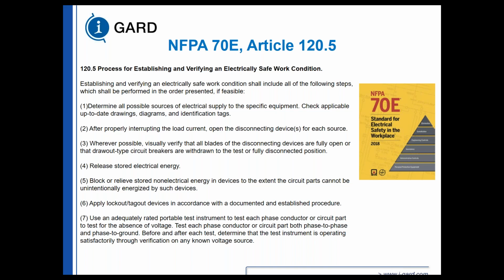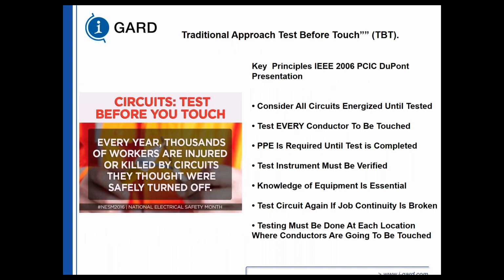We go through our job briefings and we know what we have to do, but before we can start doing these job tasks, we have to ensure that it is safe to continue work. So the traditional approach to test before touch is to consider all circuits energized until they are tested and verified that they are de-energized. Test every conductor that needs to be touched. PPE is required until the test is complete.